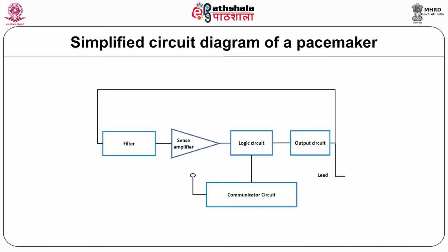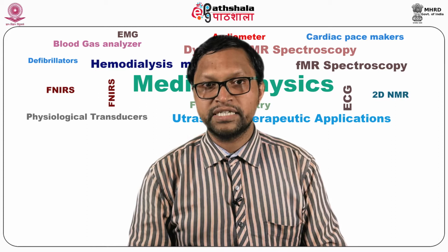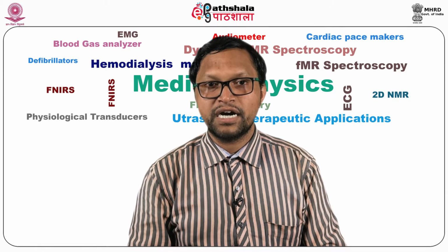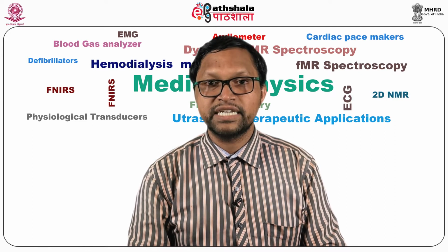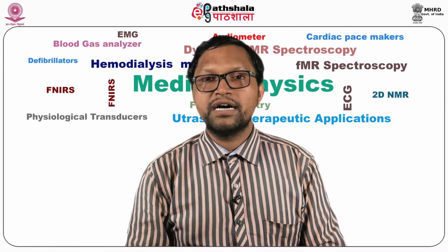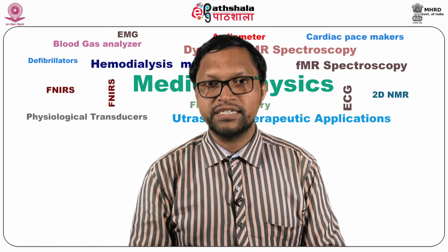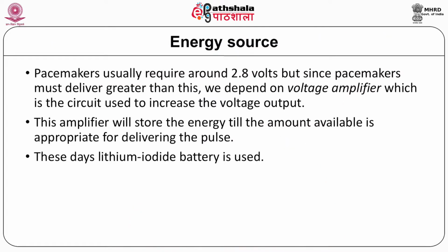The clinician adjusts these filter settings, making the device less or more sensitive, although the final signal that we get may be weak, and hence a sense amplifier is installed to boost the signal, making it large enough for the device to work with. A comparator compares the filtered and the amplified signal to the baseline, after which the signal enters the logic circuit. Let's discuss the energy source.